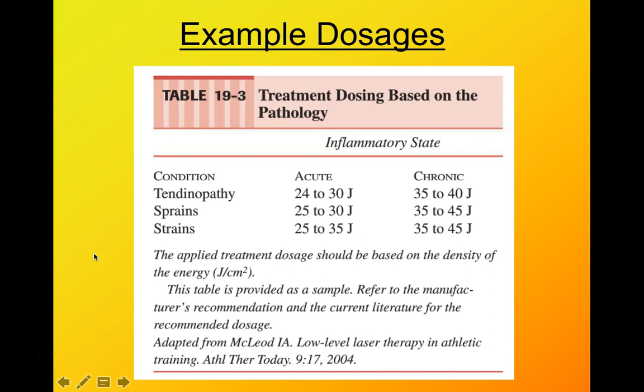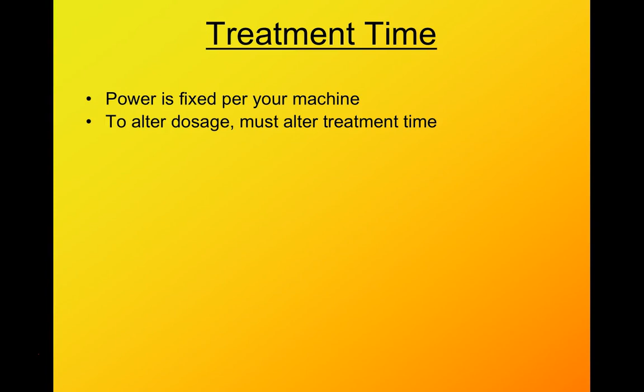So again, treatment time, when we're looking at especially our machine here, the power is fixed by your machine or by your laser. Again, there might be 2 or 3 options, or you're going to be set with your power. So also remember that this is going to potentially be affected too by wavelength. So the longer your wavelength, the deeper, the more power, usually the deeper as well. So to alter dosage, we typically alter our treatment time. So this is just a rearrangement of that equation that we have up here.